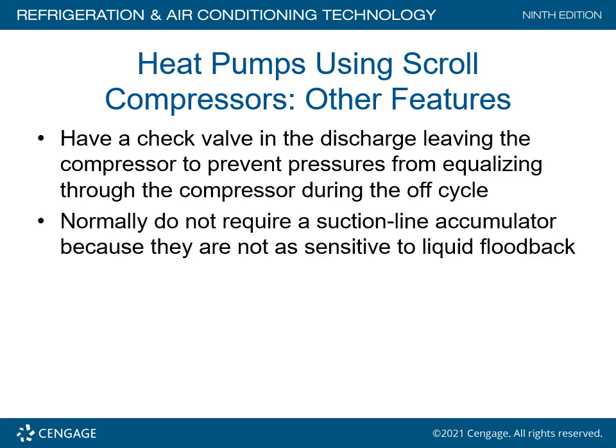Heat pumps utilizing scroll compressors have other features. They'll have a check valve in the discharge line leaving the compressor to prevent the pressures from equalizing through the compressor during the off cycle, or creating what we call a reverse rotation of the rotor, the rotating element. Normally, they do not require a suction line accumulator because they're not as sensitive to liquid floodback.